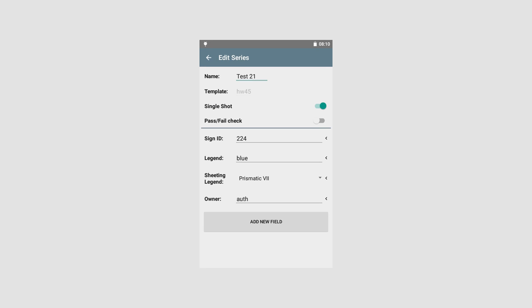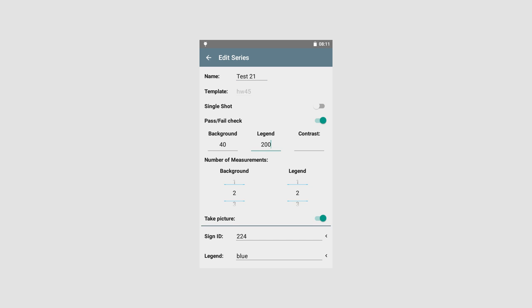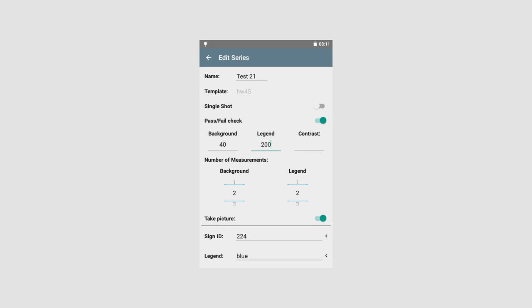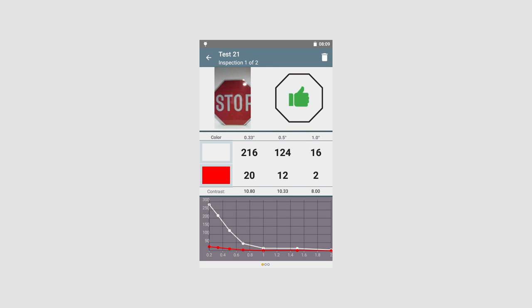In the previous selection, we decided for multiple shots. If single shot is required, we can activate this function here. Single shot can be used if just a single measurement is needed for one color. In single shot mode, no photo of sign will be available, but the pass-fail function can still be used. It will also be possible to activate manually entered pass-fail values. As an example, we have set 40 candela for background color, 200 candela for legend color, and no value for contrast. Activating pass-fail function will allow the instrument to instantly inform after each measurement if the sign has passed or failed the minimum.